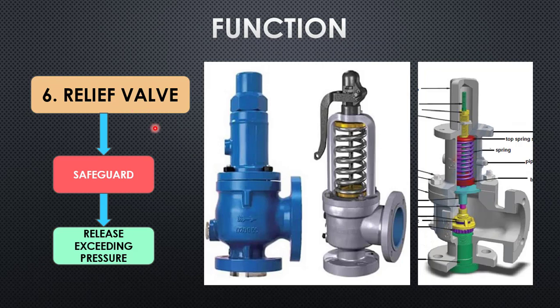The sixth valve is the relief valve, also known as a safety valve, which safeguards the system by releasing excess pressure. It contains a spring set to a specific pressure. If the piping system pressure exceeds the spring's set pressure, the spring opens the valve and releases the excess pressure. It is also known as a pressure safety valve.